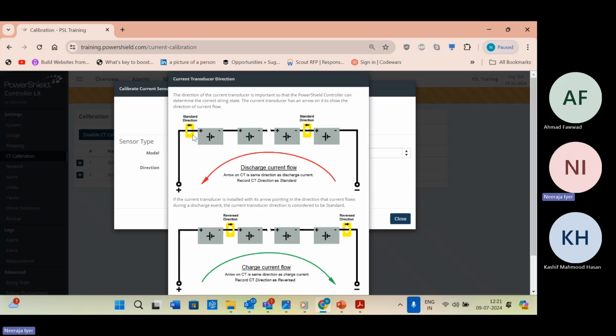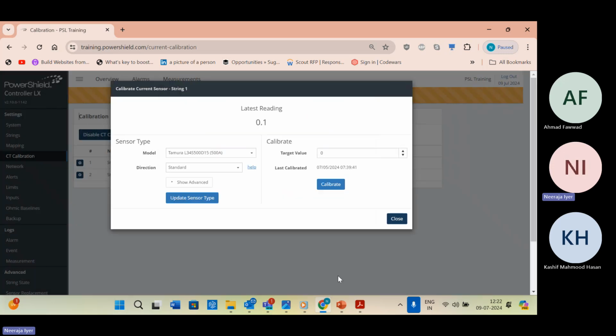Just click on the help, like you see. There is an arrow on the CT. Make sure it points from negative to positive, towards the UPS incomer positive, not the battery polarity. Regardless of wherever the CT is installed, it should always point towards the UPS incomer positive. Okay, that means it is standard. Suppose at installation this is not done, and the arrow on the nameplate of the CT is pointing to the negative of the UPS incomer. No problem. All we have to do is select reversed.